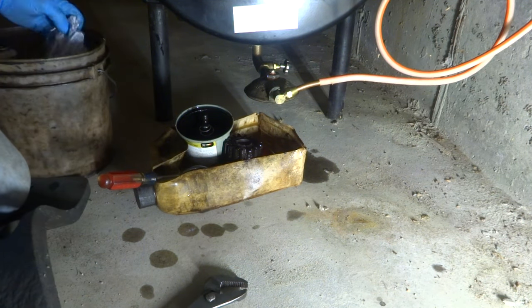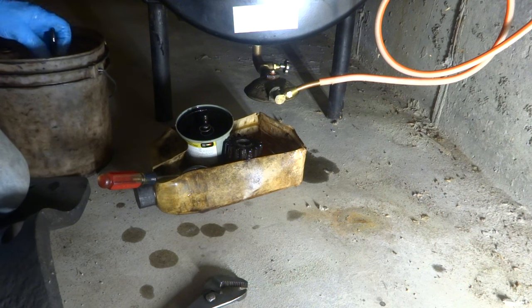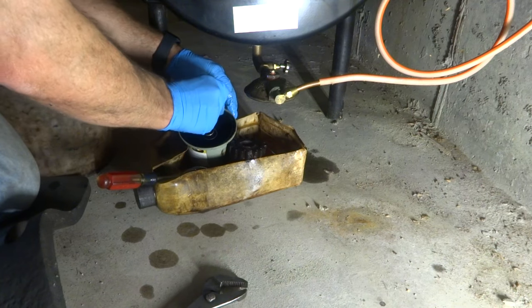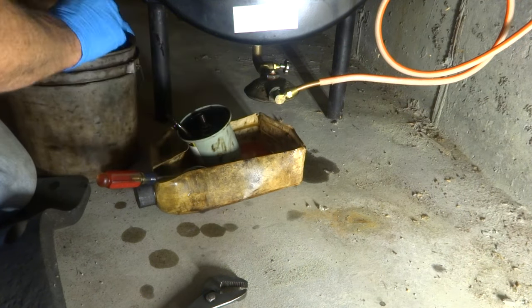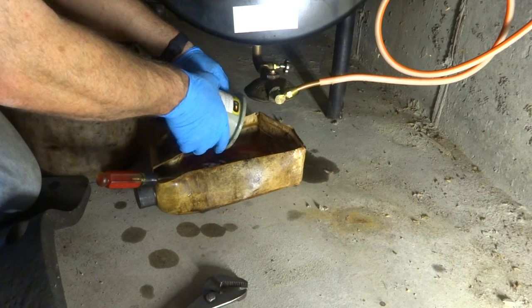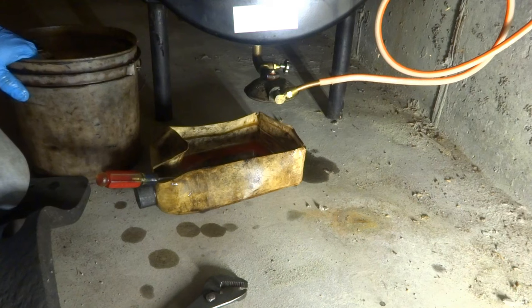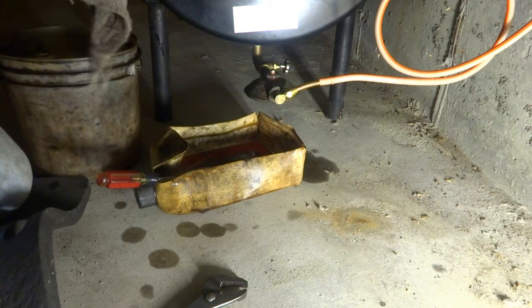Lita's got a power venter outside and she says her dog's coming in and he's getting all gray. She don't know why her dog's getting all gray. She asked the groomer, and it's pretty gnarly. The groomer says, does the dog go outside? He says, yeah. I said, well, you better check. The deck's all full of black soot. Not good.